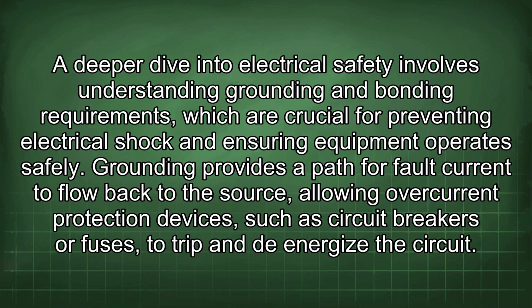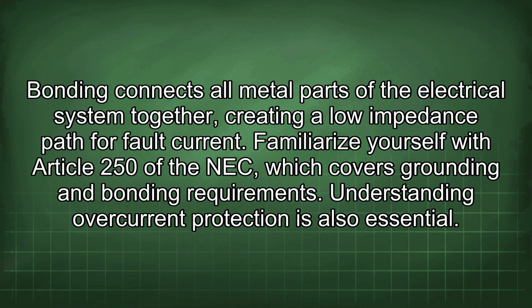A deeper dive into electrical safety involves understanding grounding and bonding requirements, which are crucial for preventing electrical shock and ensuring equipment operates safely. Grounding provides a path for fault current to flow back to the source, allowing overcurrent protection devices, such as circuit breakers or fuses, to trip and de-energize the circuit. Bonding connects all metal parts of the electrical system together, creating a low impedance path for fault current. Familiarize yourself with Article 250 of the NEC, which covers grounding and bonding requirements.